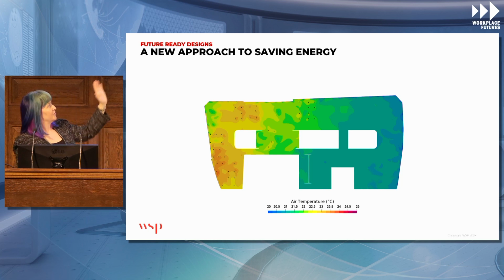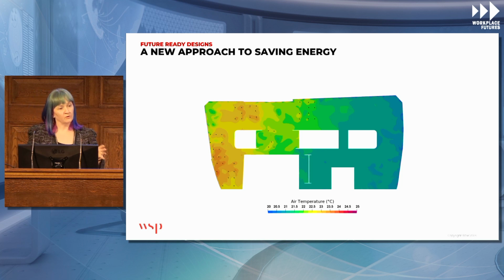And you can see then as you go down the floor, the temperature slightly cools as you get to the other end of the floor. It won't be hot or cold in the zone that's actively cooled. Intentionally just allowing the set points to vary just a little bit, by maybe 3 to 4 degrees, as you move away from the active area.